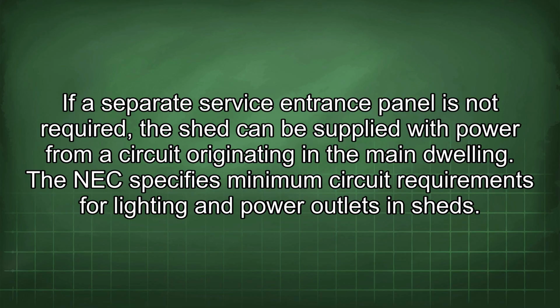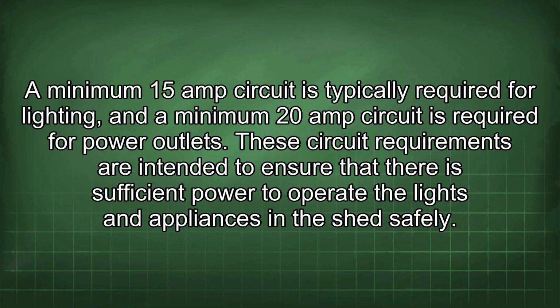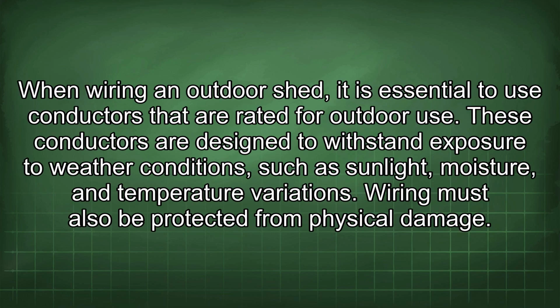If a separate service entrance panel is not required, the shed can be supplied with power from a circuit originating in the main dwelling. The NEC specifies minimum circuit requirements for lighting and power outlets in sheds. A minimum 15 amp circuit is typically required for lighting, and a minimum 20 amp circuit is required for power outlets. These circuit requirements are intended to ensure that there is sufficient power to operate the lights and appliances in the shed safely. When wiring an outdoor shed, it is essential to use conductors that are rated for outdoor use. These conductors are designed to withstand exposure to weather conditions such as sunlight, moisture, and temperature variations.